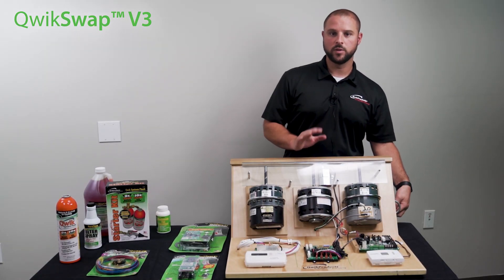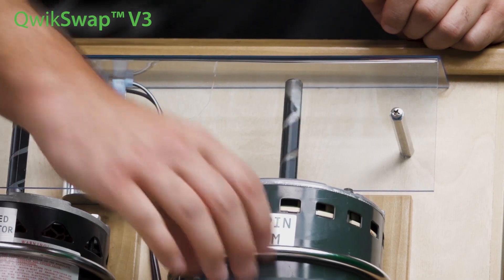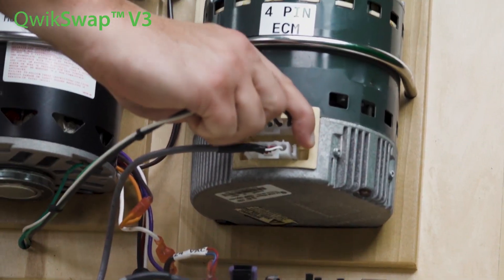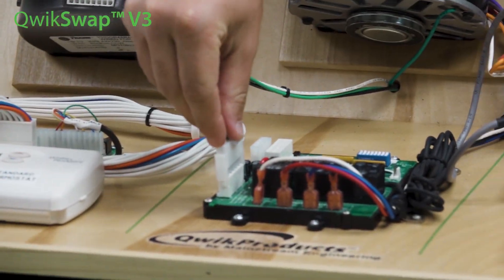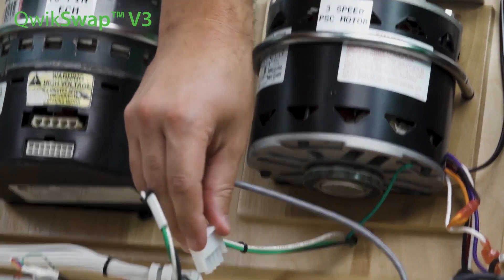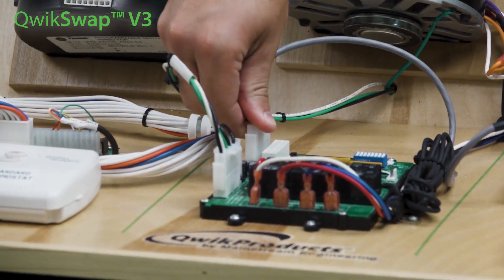So I'm going to turn this off to simulate the motor breaking down. What I can do now is take the power plug off of the 4-pin ECM and plug it onto my QwikSwap V3. Then I take the 4-pin communication plug and plug it onto the QwikSwap V3. And then I run the common, high, medium, and low to a standard PSC motor.